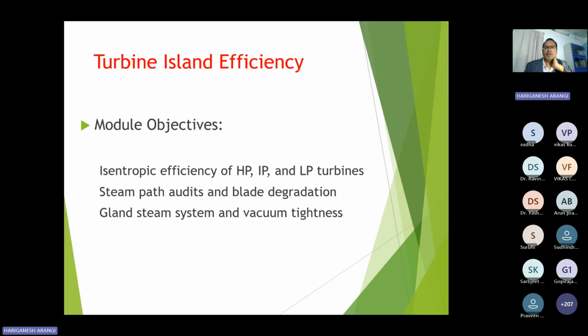Turbine efficiency is affected by the isentropic efficiency of HP, IP, and LP turbines, steam path audits, and blade degradation. Several times, due to the low temperature of the steam, it degrades the inside of the turbine blades. Even the turbine blades get eroded. It will be like a rat biting. Or if the water parameters are improper, where the phosphate and silica are more, then it will be coated on the turbine blades. When the coating is more on the turbine blades, to drive that again you need more energy, like more steam. Again it is a loss.